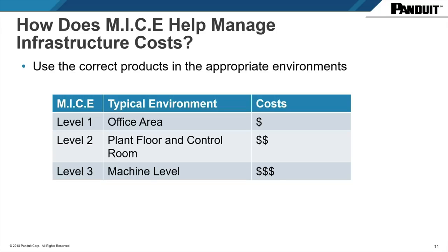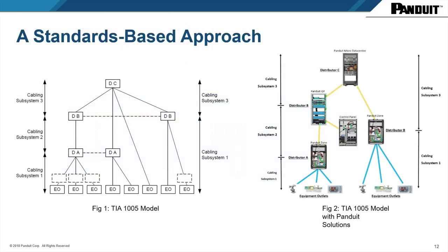So we could potentially be using commercial grade product inside of a factory if we have the right protection for each and every one of those systems. Enclosures, for instance, can be those types of protections. Inside of an enclosure, you could put commercial grade product as long as the enclosure is made out of stainless steel and it's got the right gasketing so water and dust cannot get into these systems. These are the things we will always apply, which is common sense when we're running these systems.